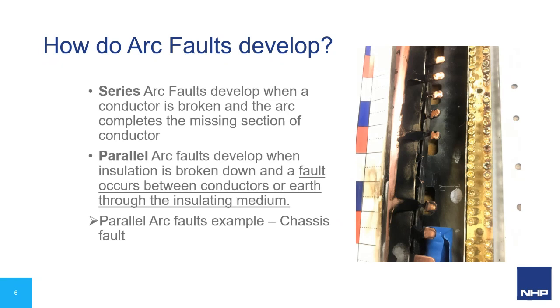A series arc fault is a little bit different. That's where you get a broken cable and the power continues to flow through that conductor, even though it's broken. Very common to see. A good example is in solar DC systems, where the solar panels effectively act as a current source and it keeps pushing that current through. But in general, in power distribution applications where we see these large arc faults, usually it's a parallel arc fault that we're talking about. So let's go back to that original case.